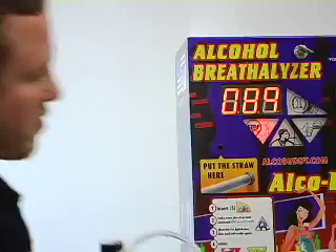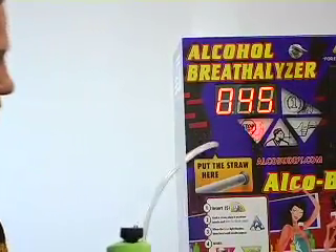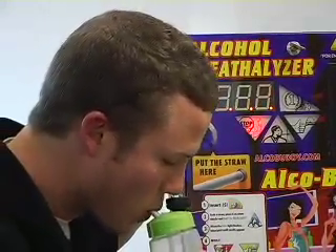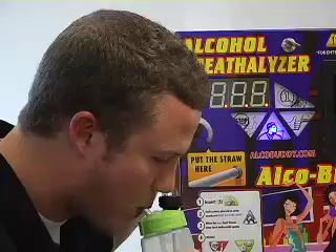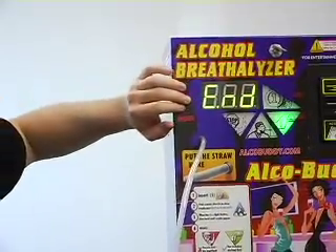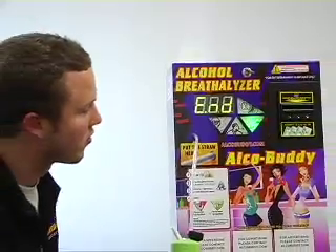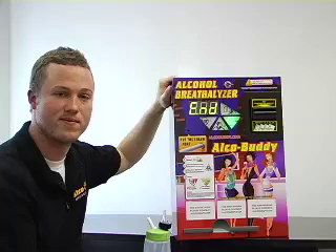We will wait for the next 10 second countdown, hook up the tube, and get ready to blow. Perfect — as you can see, we hit our range: 0.33. In that case it flashes green and it will also show 'end', which means it is saved and now the machine is calibrated and ready to go.